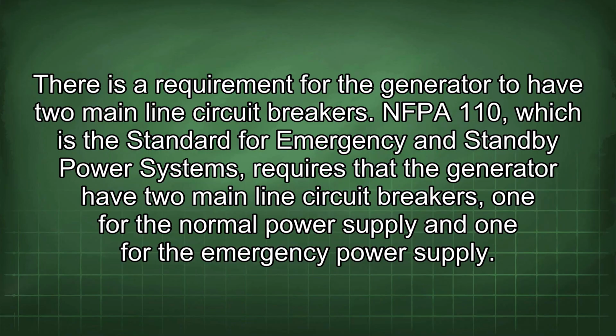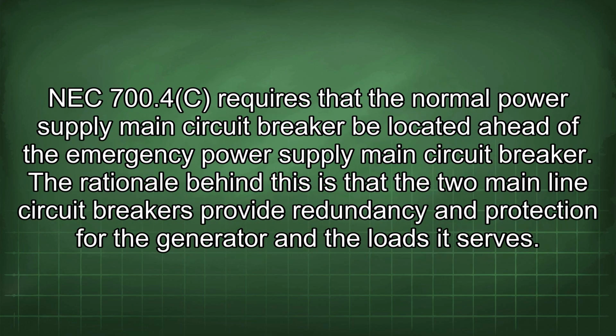There is a requirement for the generator to have two mainline circuit breakers. NFPA 110, which is the standard for emergency and standby power systems, requires that the generator have two mainline circuit breakers, one for the normal power supply and one for the emergency power supply. NEC 700.4c requires that the normal power supply main circuit breaker be located ahead of the emergency power supply main circuit breaker. The rationale behind this is that the two mainline circuit breakers provide redundancy and protection for the generator and the loads it serves.